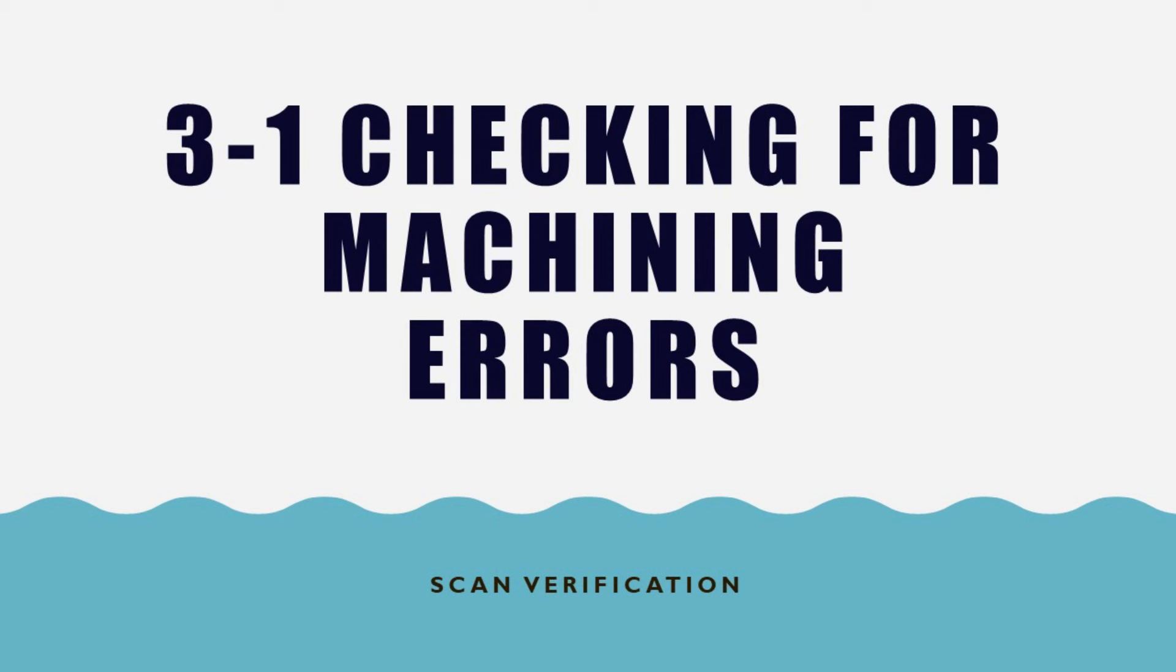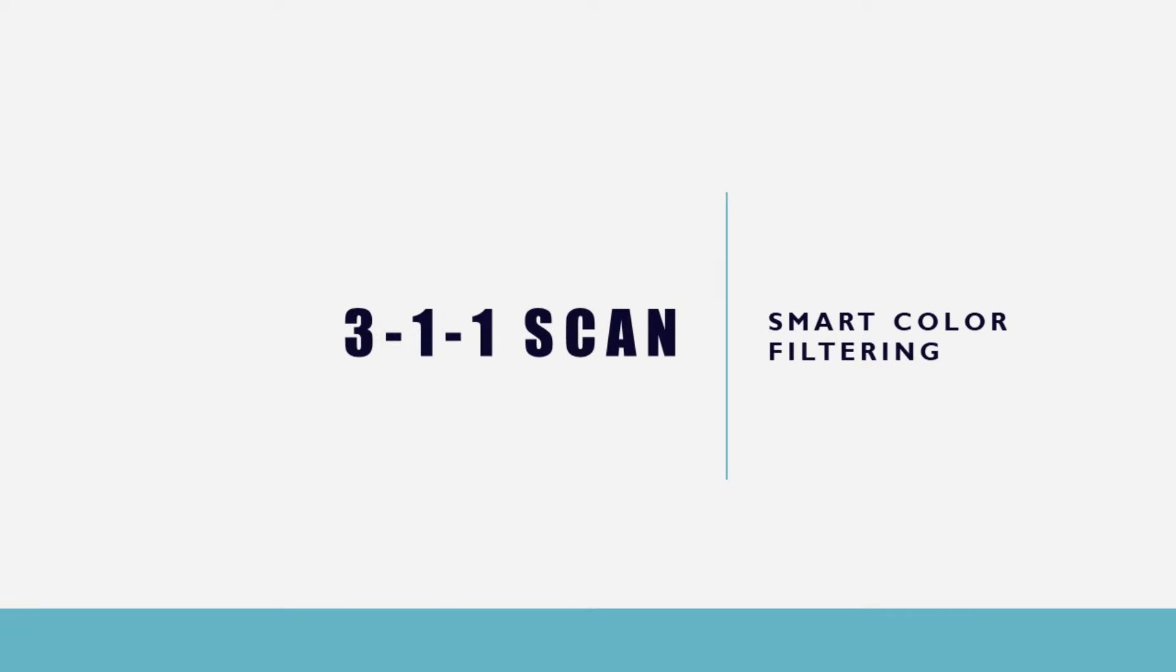In contrast, the method I'm going to introduce today is fairly simple and useful. All you need to do is scan the machined crown and overlay it with the design file for comparison. Maintaining your machine this way is very productive because you don't have to fit every crown that you machine. Let's explain how to scan.